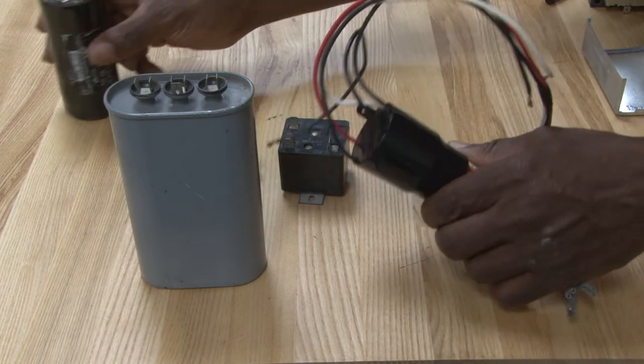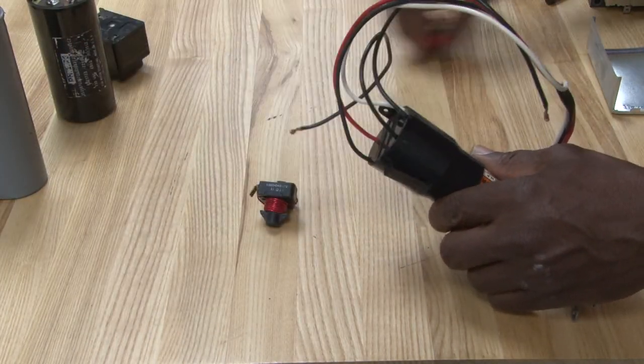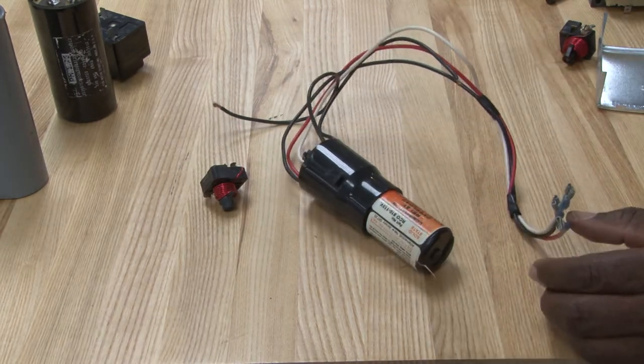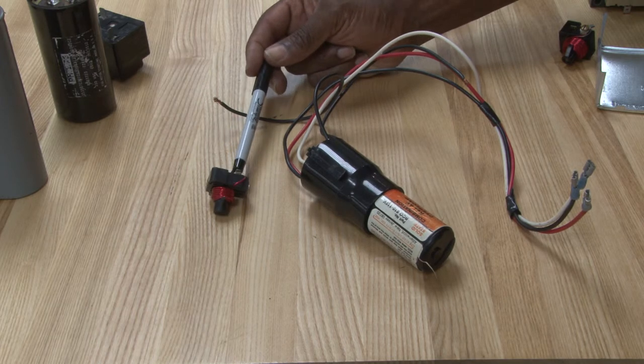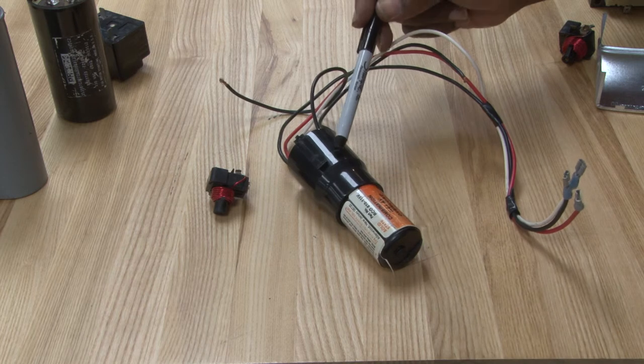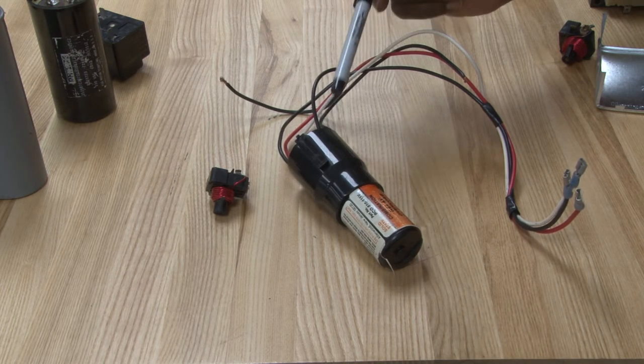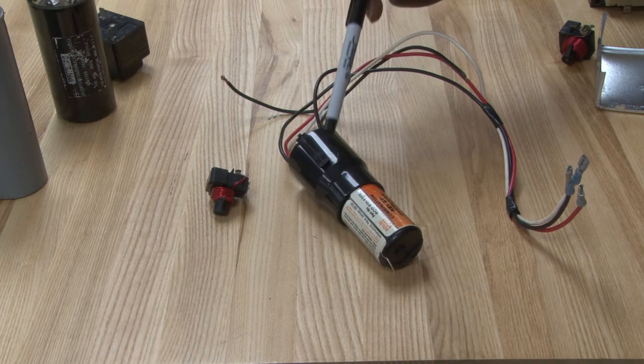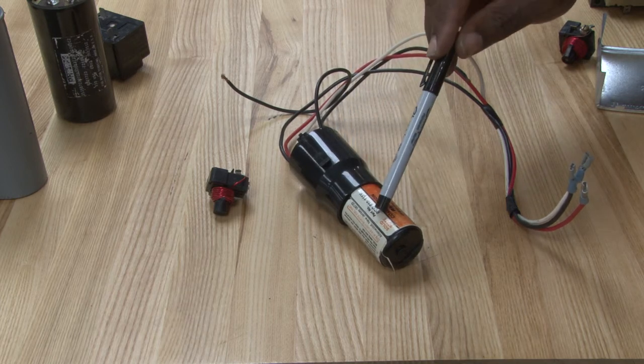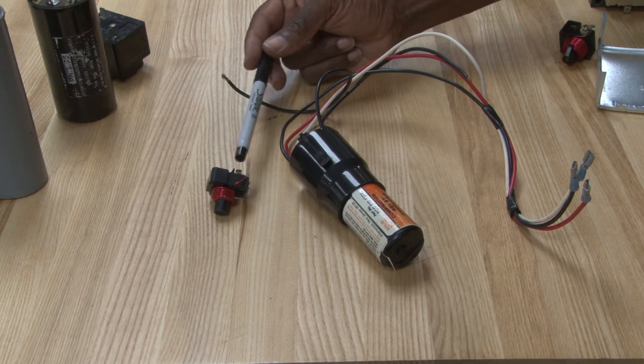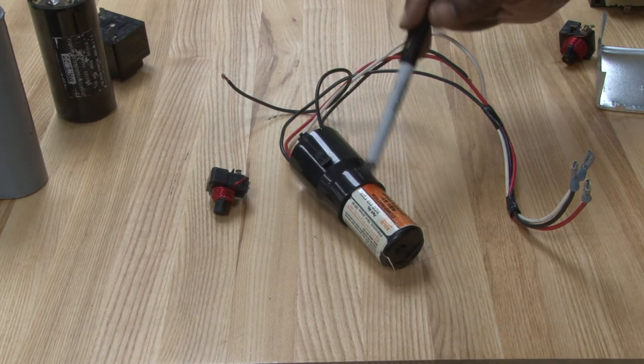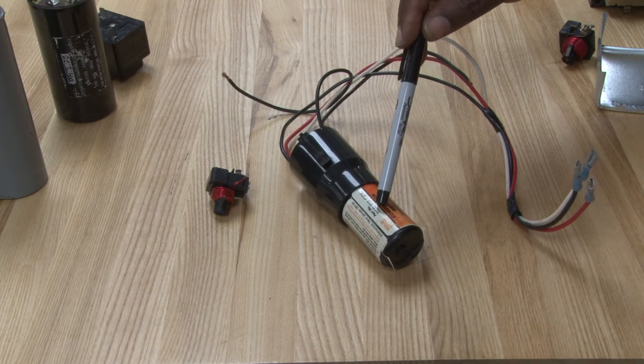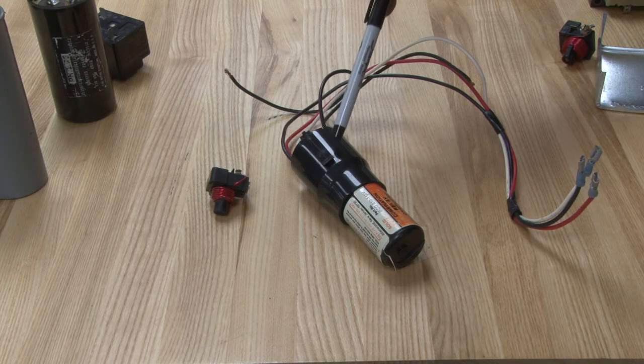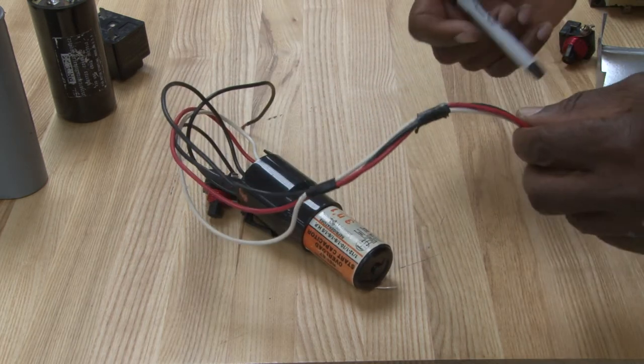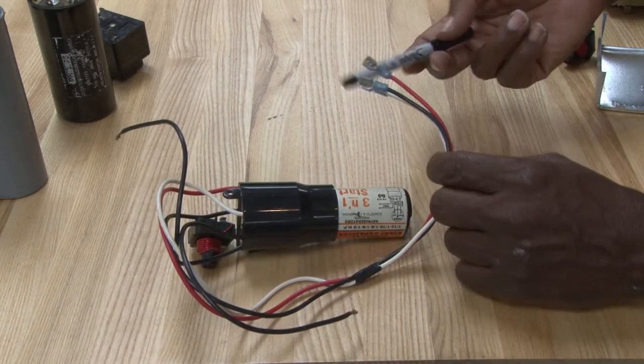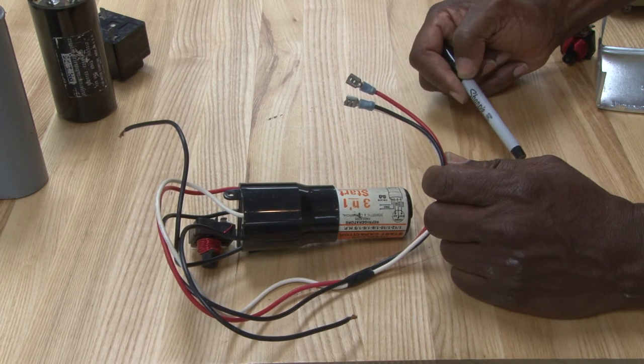And there's a solid state relay for small refrigeration, small refrigeration type compressors. They would use this type of relay, but if this ever goes bad, most technicians would carry this on their truck. This is a solid state relay. As a matter of fact, it's a combination relay. It's a relay, overload protection, and it also is a start capacitor. It's 3-in-1. So when this goes bad, you can replace it with a system that's actually even better. There are no moving parts, but it comes with a start capacitor to give it extra starting torque, and it has a built-in overload also. Basically, you just have these wires that go to your compressor leads, and you would use these three terminals to power up your compressor.